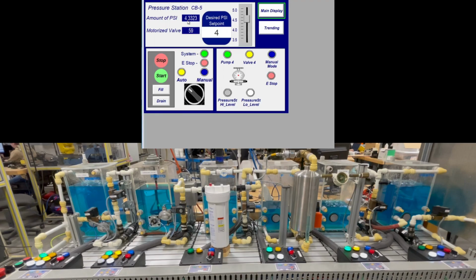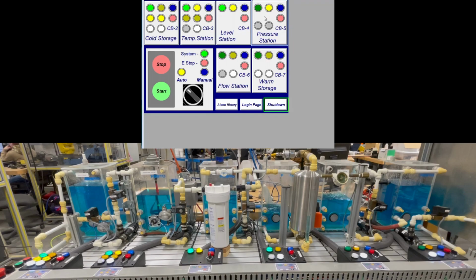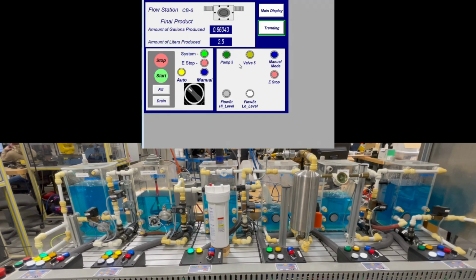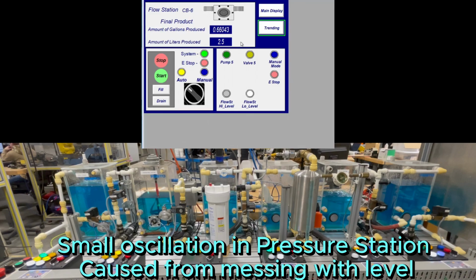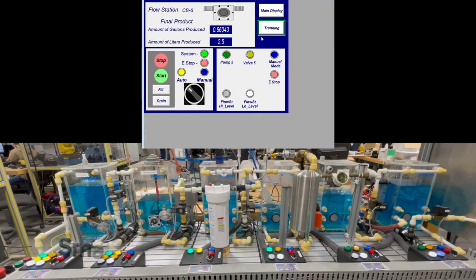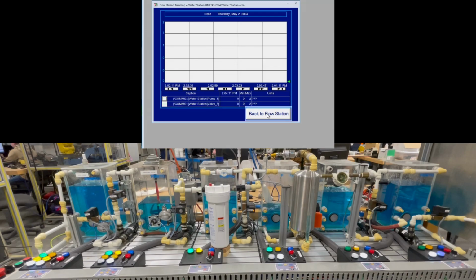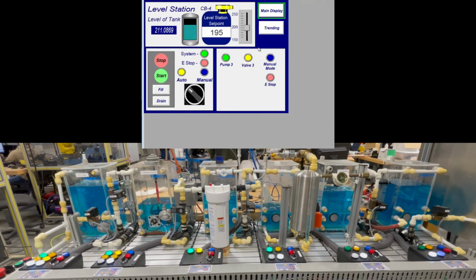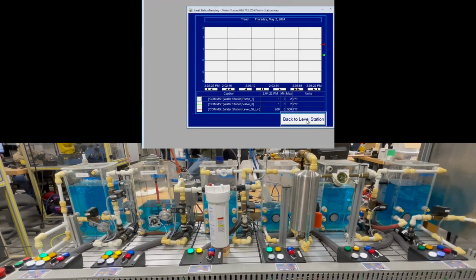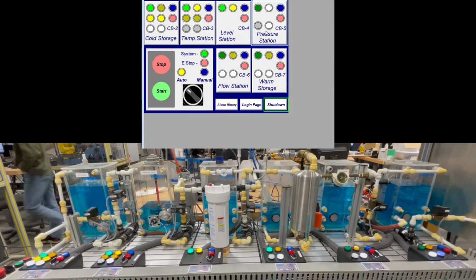The pressure station, you can see it sits at 4.5 right there. Seeing around 4.4, 4.5, it just differentiates just a little bit. You can see that motorized valve opening up and closing. The flow station is recording all of the amount of liters and gallons produced. And here is a trending for that. See that bar going up and down because the level of the tank is changing, going up and down. Here's the trending for that one.